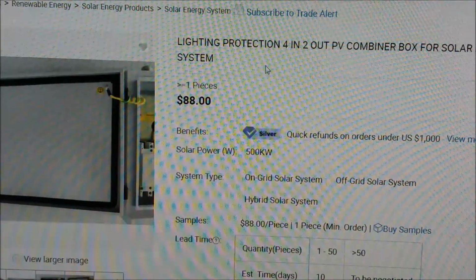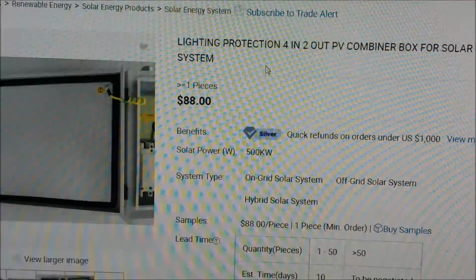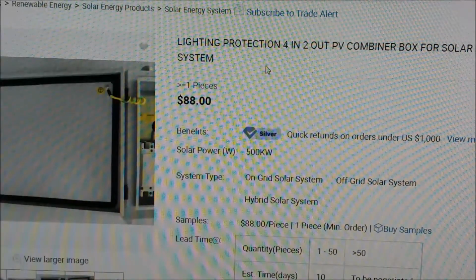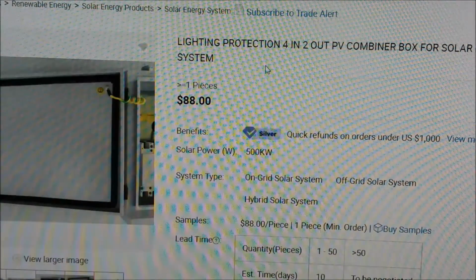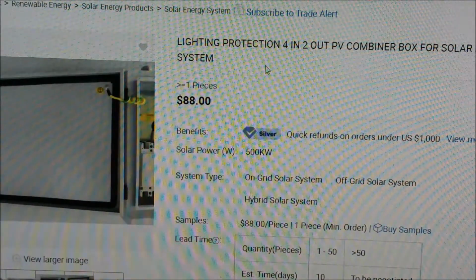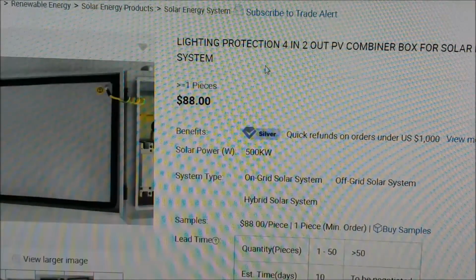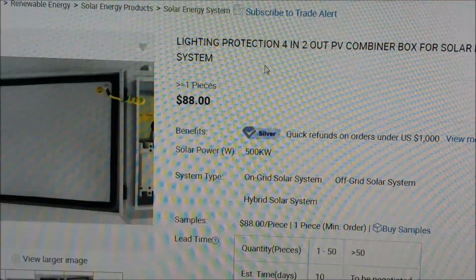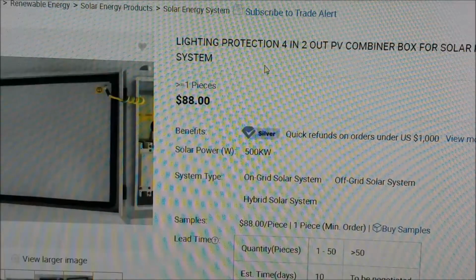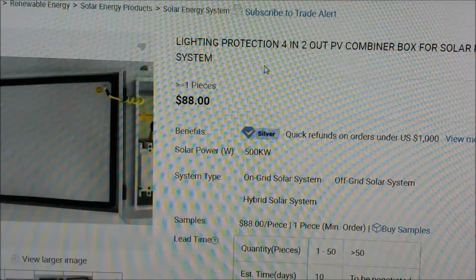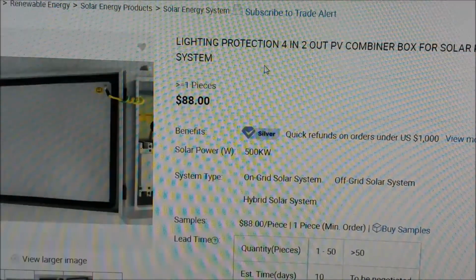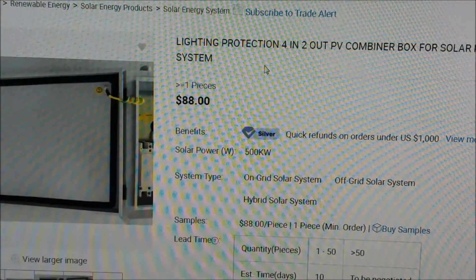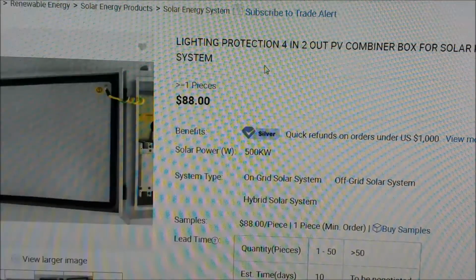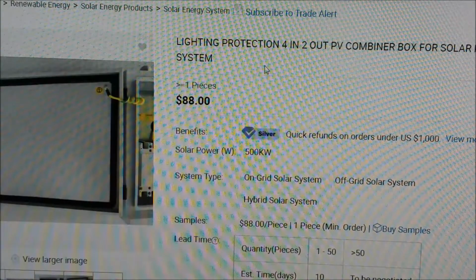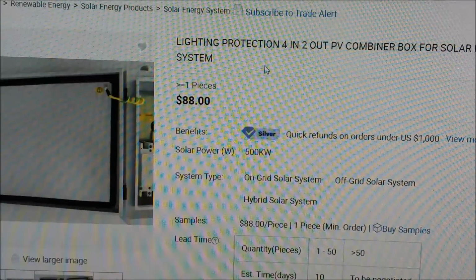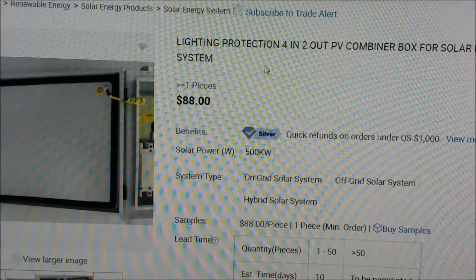So if you want to not combine them - because what we want to do is put 1 string on an inverter, and actually we're splitting a string to 2 inverters. It'll be the left channel. One of them will be left channels on 2 inverters, and the next string will be the right channels on those same 2 inverters. That way it minimizes the amps that any one inverter has to dissipate heat from.